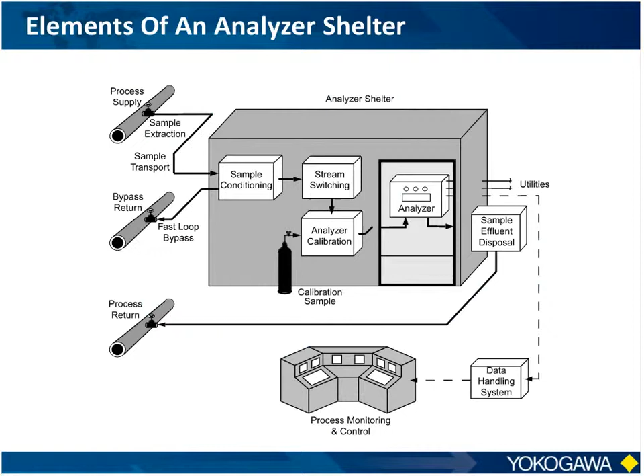The next aspect is that most analyzers involved in these types of projects are some type of extractive analyzers. In other words, we're taking the sample out of the process, cleaning it up, getting the right temperature and pressure, perhaps switching in a calibration gas or a zero and span gas to make it available to the analyzer when appropriate. Again, there might be some calibration gases involved.